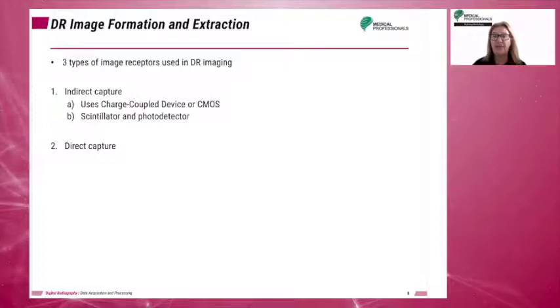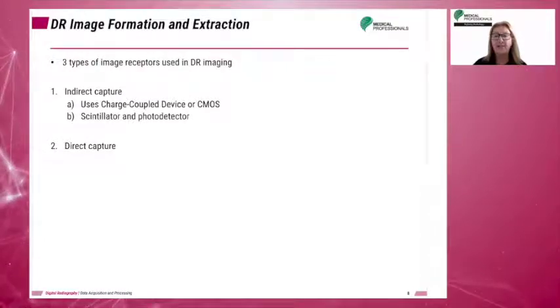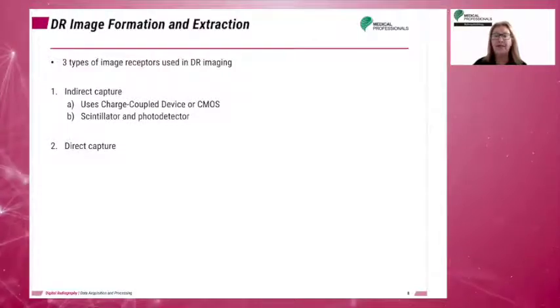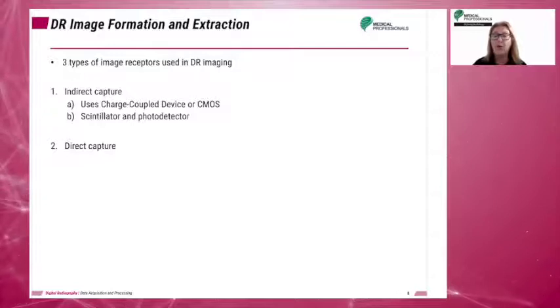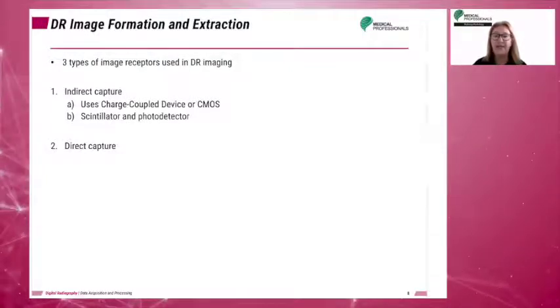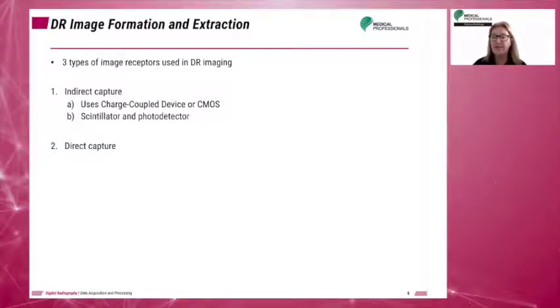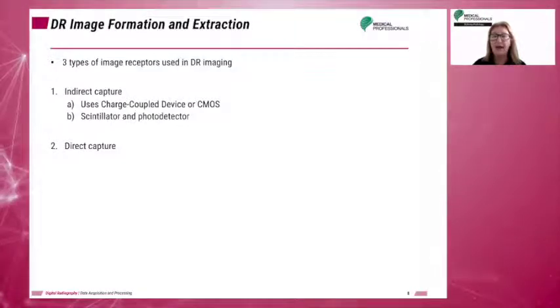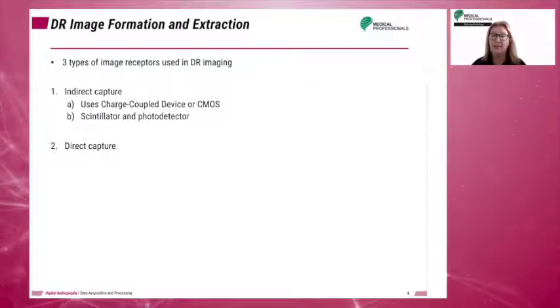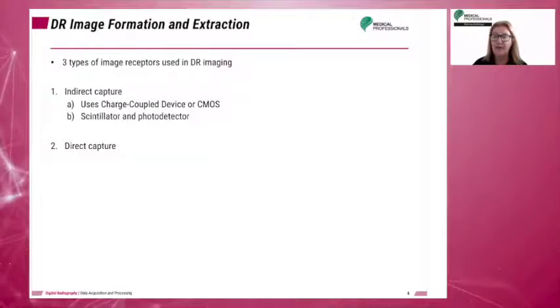The second indirect method involves the use of either cesium iodide or gadolinium oxysulfide as a scintillator coupled to a photodetector — amorphous silicon — and a thin film transistor. The TFTs are arranged as a network of pixels or detector elements, with each detector element containing a photodetector with a TFT. In this system, the scintillator produces light from X-ray photons. The light is absorbed by the photodetector and converted into an electronic signal that is collected by the detector elements and passed to the ADC to be digitized.